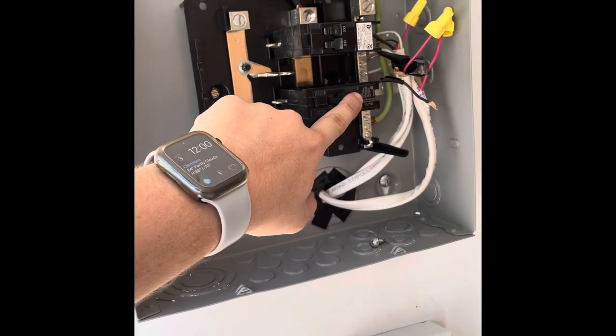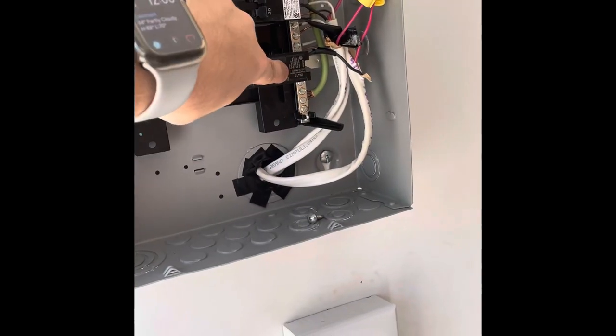We'll go ahead and test one more. Let me disconnect the power here — we're going to test another outlet on this side, because I jumped a wire from here, which is like my home run box, all the way down to the back. I thought about putting an outlet on the back side and I eventually did, so let's see if we wired this one up correctly. Once we switch this big breaker on the bottom that powers the right side — we're all good, no trip. You can see two orange lights right there, so this is all wired up correct.